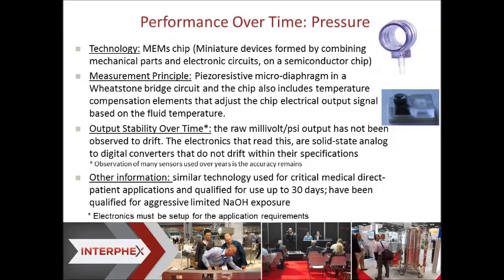The sensing technology in our pressure sensors is a MEMS chip, a miniature electronic device formed by combining mechanical parts and electronic circuits. The measurement principle is a piezo-resistive diaphragm in a circuit, and it has an electrical output signal that's compensated for temperature also. According to all the work we've done in documented information, the raw signal output of this chip is millivolts per PSI, and it has not been observed to drift at all over time, even over years. And the electronics that read this and the MEMS are solid state analog to digital converters that don't drift within their specifications.